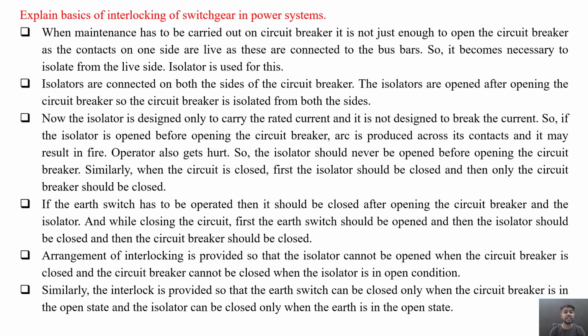If the earth switch has to be operated, then it should be closed after the opening of the circuit breaker and the isolator. And while closing the circuit, first the earth switch should be opened, then the isolator should be closed, and then the circuit breaker should be closed.